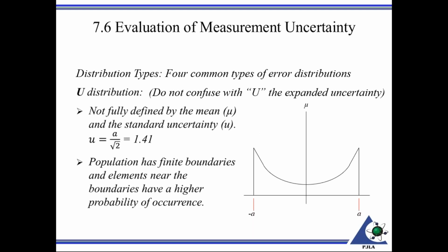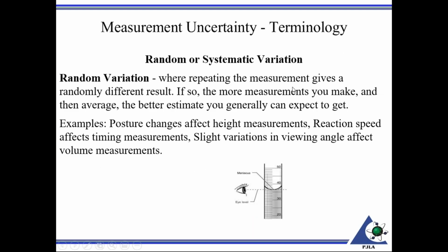So for example, if you have temperature controls, let's say 20 degrees C plus or minus 2 degrees C, the temperature would change as it gets closer to the boundaries. Say it's cooling down when it gets closer to the cooler boundary, then the heat would kick on there. So hence boundary driven as opposed to center driven. About uncertainty, make sure I didn't skip a slide there. I just want to also discuss random versus systematic variation.